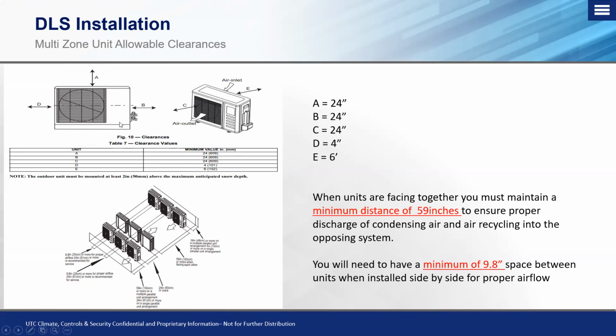D, which is going to be from the left side of the unit, the coil, out to whatever nearest obstacle, if there is one, is 4 inches. Now again, this doesn't mean cram this against the wall until it's 4 inches. You still have to get into that coil to do coil cleanings on it and also get around for service access. So again, that's the minimum. Typically about 12 to 24 inches is usually what I recommend for point D.